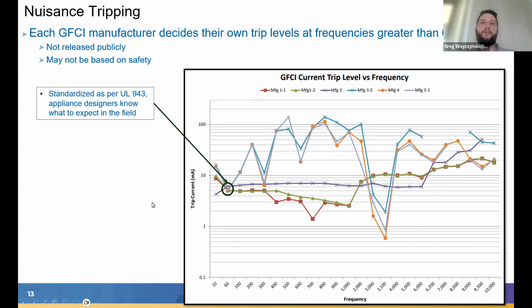So a few other things about this graph. We see a nice clump here. All the different GFCI models at 60 hertz are tripping in that same band. That's great. We want them all to be condensed so we know what to expect in the field. As appliance designers, we want to know how the GFCI is going to perform in the field, and seeing something like this is great because we know what to design around. The reason this big clump is here is because the UL standard requires it. At 60 hertz, you have to trip between these levels and you shall not trip below certain levels.